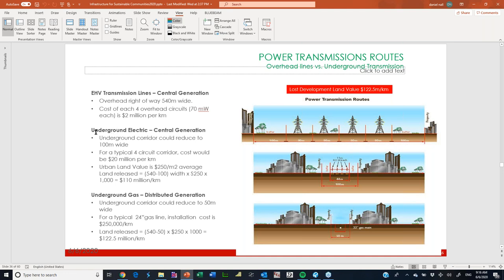The underground electric corridor would be reduced to 100 meters wide. For a typical four circuit corridor, the cost would be $20 million per kilometer. The urban land value is $250 per square meter, so the land released from moving from overhead transmission lines to underground electric would be $110 million per kilometer.